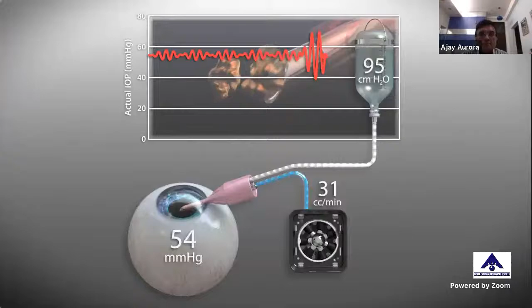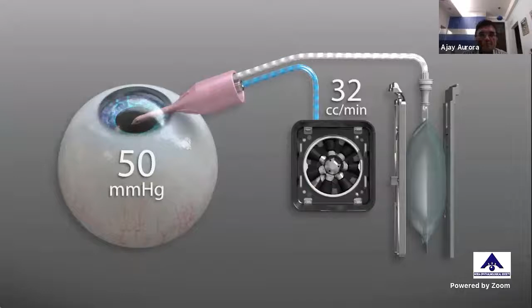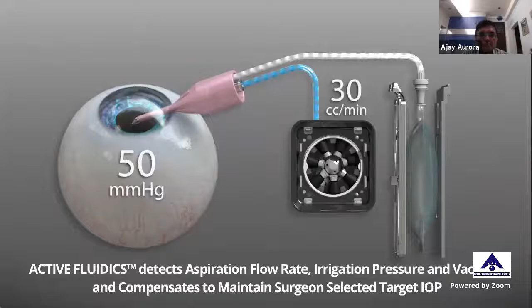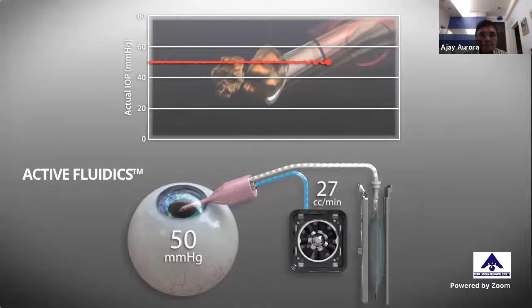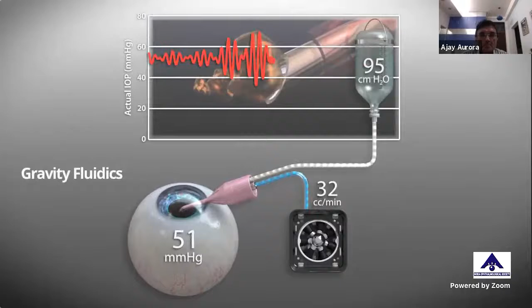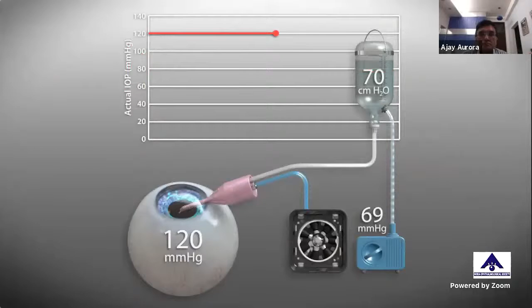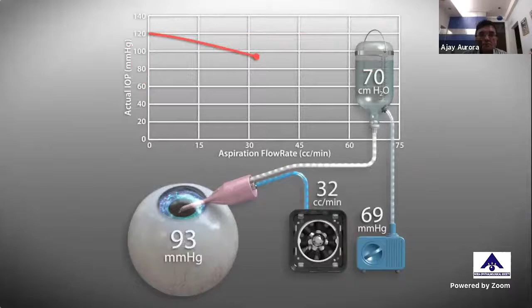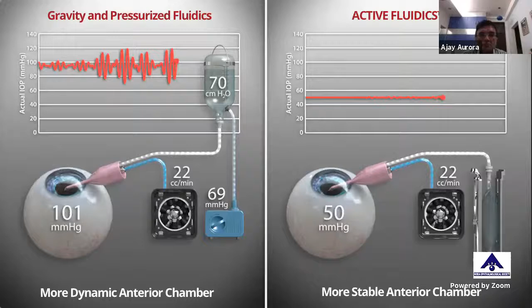of the phaco tip. The Centurion Vision System's active fluidics technology is able to detect flow rate, irrigation pressure, and vacuum, and compensates for the pressure loss by squeezing the BSS bag more to help maintain the surgeon-selected IOP. This results in a more stable anterior chamber. With gravity fluidics, since the fluid source via the bottle height is static, pressure in the anterior chamber is dynamic. With active fluidics technology, since the fluid source is dynamic, the anterior chamber is much better able to maintain stability. Now, some surgeons use an air pump to achieve high irrigation pressure in the bottle, similar to a high IV pole. This will generate a very high initial IOP value. That value will then decrease with flow. This is very different from active fluidics, where a much lower IOP value can be targeted and maintained.